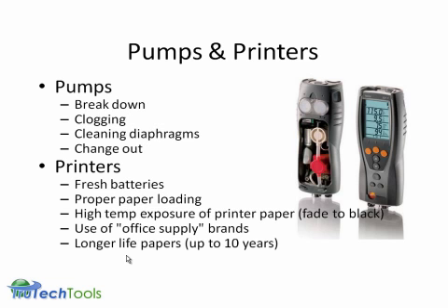Pumps and printers. The pumps are replaceable. They very rarely ever break down, but they can get clogged, and I have seen them get clogged with something stuck in the diaphragm. You can pop that pump apart, clean the diaphragm off, and put it right back together. So it's not a hard job to do. We can handle that in service for you if you're not comfortable doing that.